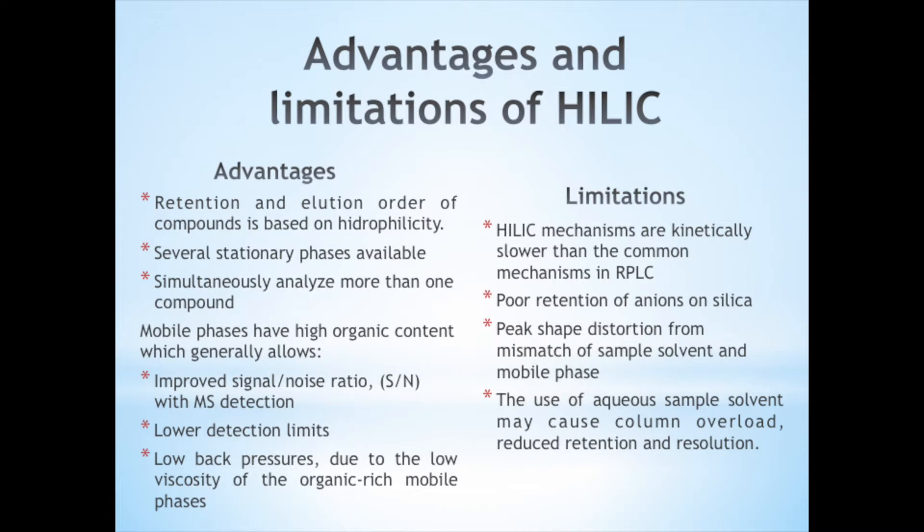On the other hand, this technique has its limitations. HILIC mechanisms are kinetically slower than the common mechanisms in RPLC. There is poor retention of anions on silica. Peak shape distortion can occur from mismatch of sample solvent and mobile phase. Also, the use of aqueous sample solvent may cause column overload, reduce retention and resolution.